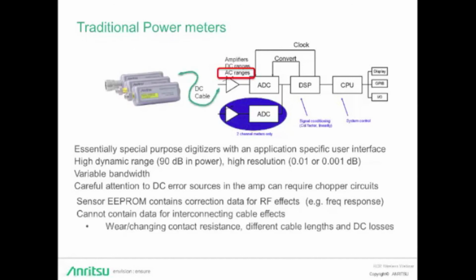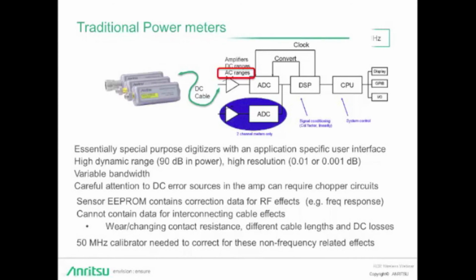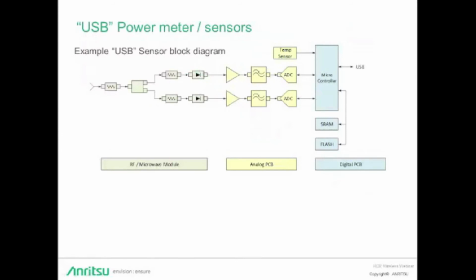However, neither the sensor nor the meter can know the length of the cable being utilized to interconnect them or its performance level. So to characterize the interconnect, that is, to account for any wear or change in contact resistance, different cable lengths, DC losses, etc., power meters are often equipped with a reference signal, typically a 50 megahertz source. Before making a measurement, the user would connect the sensor and its cable to the source to correct for any non-frequency related effects. So now let's compare that to USB sensors.